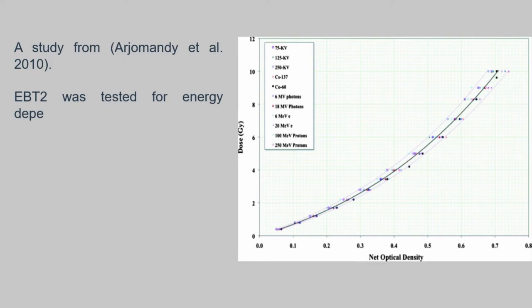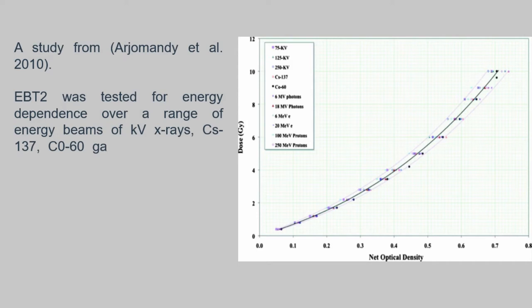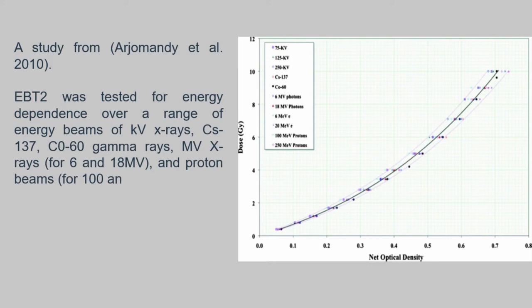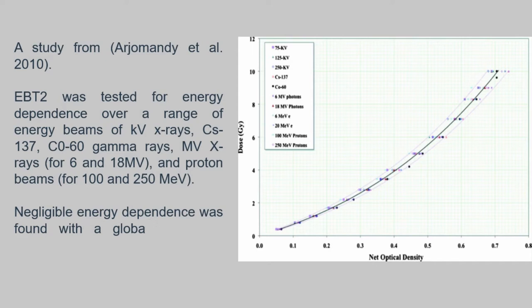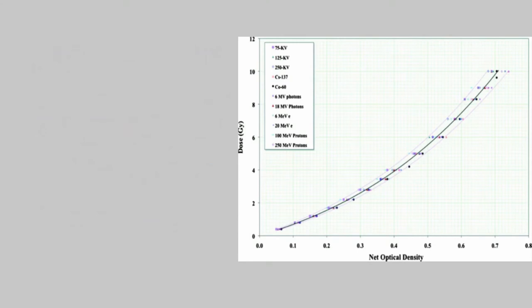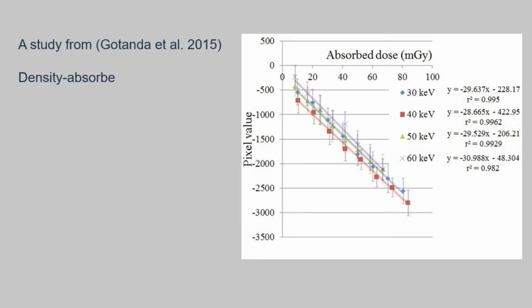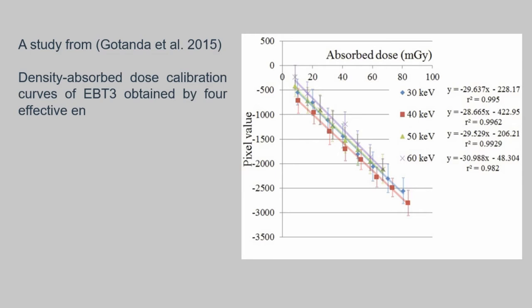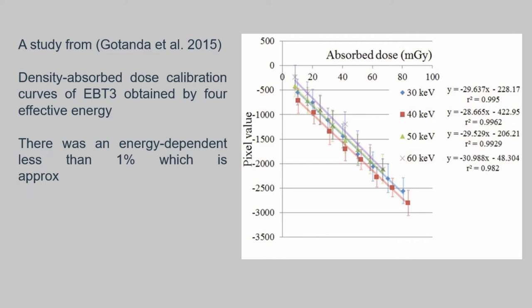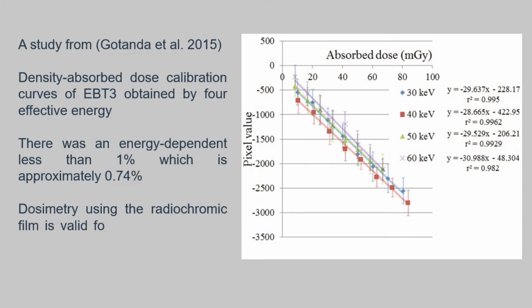A study from Arjomandy et al. in 2010 tested EBT2 for energy dependence over a range of energy beams including kV X-rays, Cesium-137, Cobalt-60 gamma rays, MV X-rays for 6 and 18 MV, and proton beams for 100 and 250 MeV. Negligible energy dependence was found with a global spread of plus or minus 4.5% for all energy beams. Another study from Gotanda et al. in 2015 obtained density-absorbed dose calibration curves for EBT3 at four effective energies: 30, 40, 50, and 60 keV. Energy dependence was less than 1%, approximately 0.74%, concluding that dosimetry using radiochromic film is valid for effective energy in the diagnostic range.